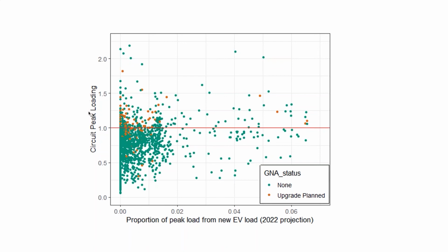Here we have the actual circuit peak loading, which is what PG&E has in their models as the percent of the capacity of the feeder that each feeder hits. For example, this is a feeder with a lot of EVs modeled in it, so 6% of that peak load is from charging. It's also already somewhat overloaded, at 1.25, meaning at summer or winter peak, on certain days, it might go 25% over its capacity.